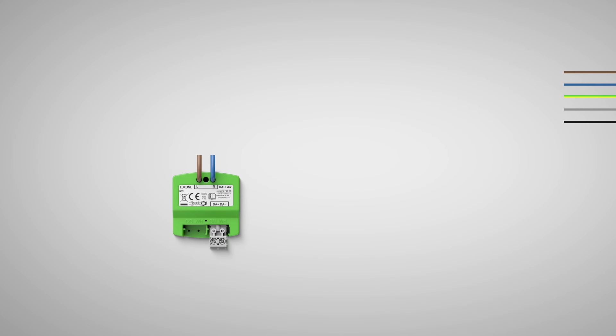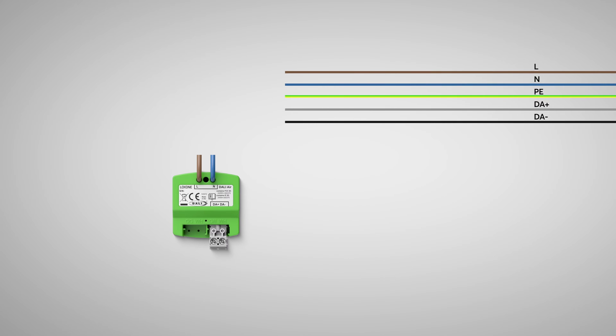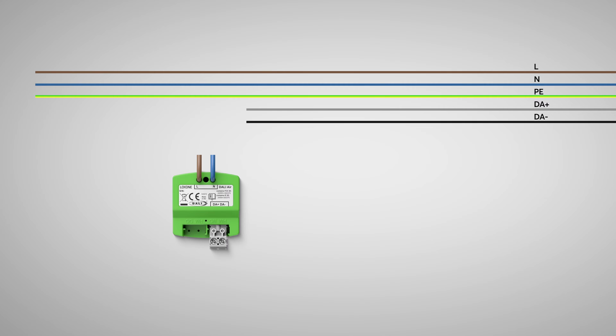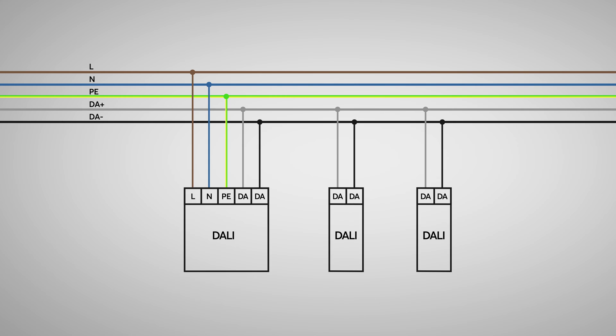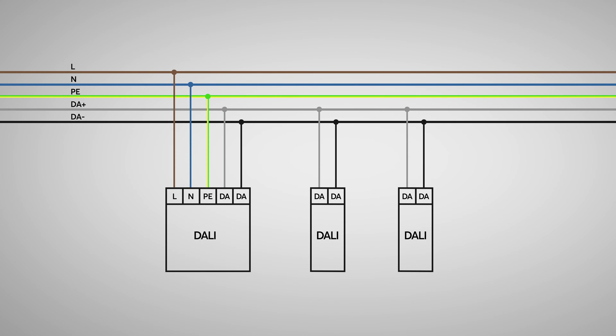Let's take a closer look at the wiring of the Dali Air. The DALI 2-wire technology is usually laid parallel to the 230V in the same cable. The Dali Air is powered via the two wires — brown and blue — with 230V. The two remaining wires, black and grey, are used for the data connection, which is not polarity bound. This means it doesn't matter how the data lines are connected, and Dali Air has an internal power supply which is also transmitted via the data line.